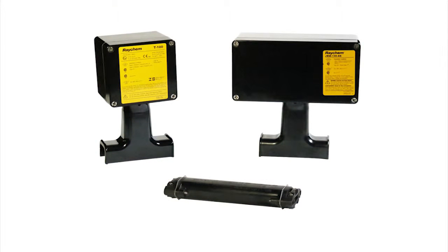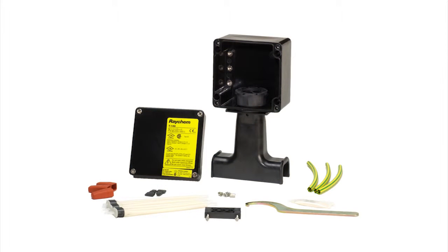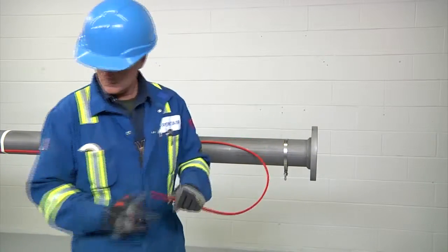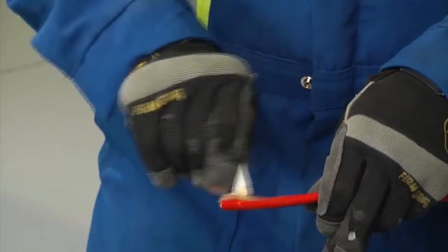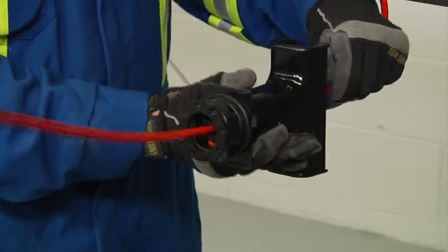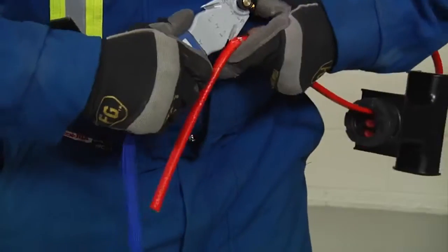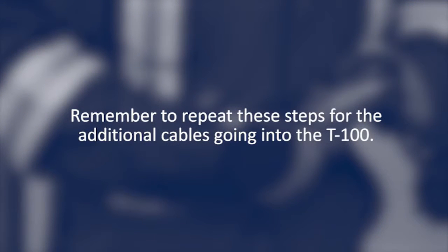There are two types of kits used for a T or splice — above insulation or below insulation kits. We will demonstrate the above insulation kit. The Raychem T100 is an above-insulation splice or T connection kit. Allow 24 inches (600 millimeters) of heating cable for installation. Cut off the heating cable end at about 45 degrees, apply lubricant for easier insertion into the stand, and insert 18 inches (450 millimeters) of heating cable through the stand. Square off the cable end with a 90-degree cut, but do not attach the stand to the pipe yet, and proceed to stripping the end of the cable as previously shown. Repeat these steps for the additional cables going into the T100.